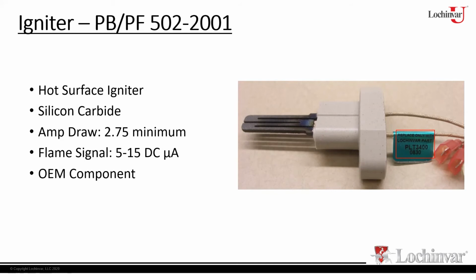As it starts to heat up, it changes the amp draw. The amp draw characteristic changes. Now, there is a threshold that the module is looking for before it will start a timer. In this case, that threshold is 2.75 amps. So when it sees that, it says, all right, I've drawn the amperage I'm looking for. I'm going to start a timer. It's basically a 20-second timer. That's to ensure that as long as that igniter stays above 2.75 amps, it will get hot enough within that time to light off your gas air mixture.